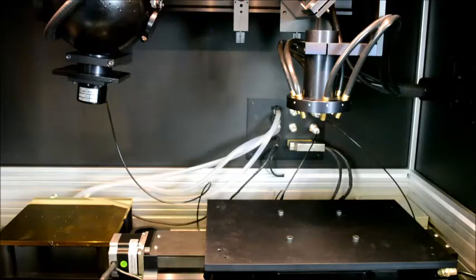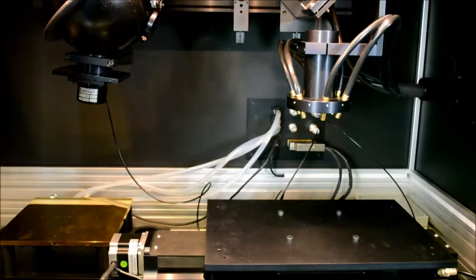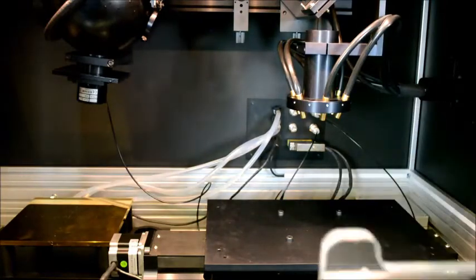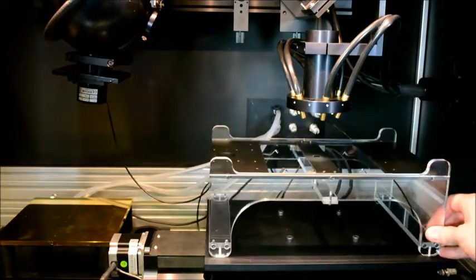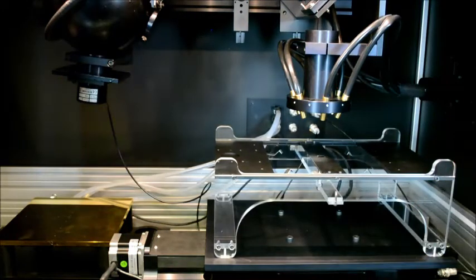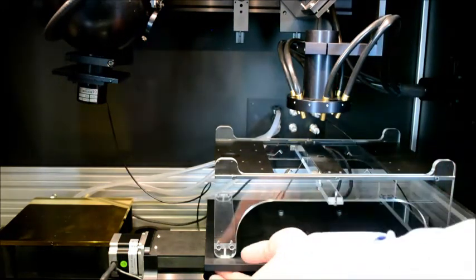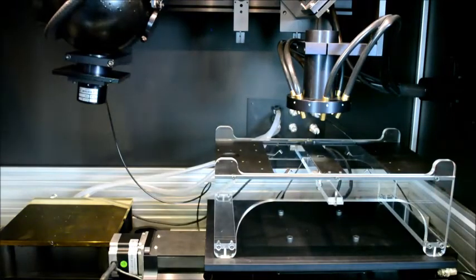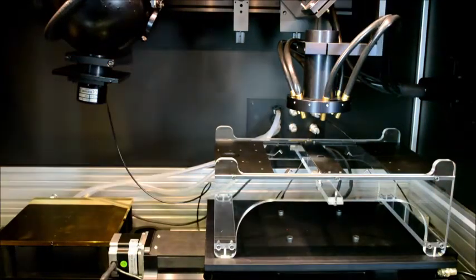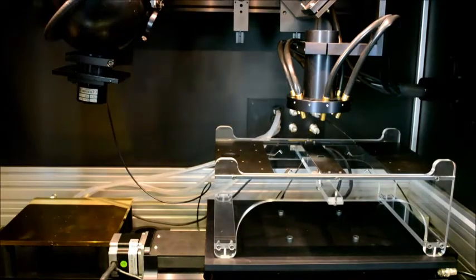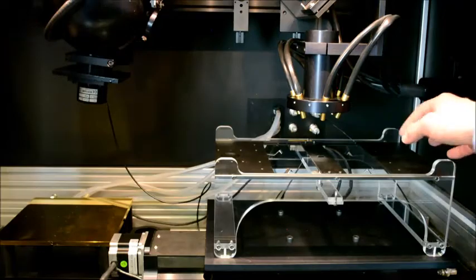One should be careful, of course, that the pipes of the water cooling circuit do not impede the movement of the motorized XY stage. The superstrate chuck can be mounted on the motorized XY stage in this manner and fixed in place at each corner using 4 M2.5 screws. The superstrate chuck allows one to mount samples from the inverse side.